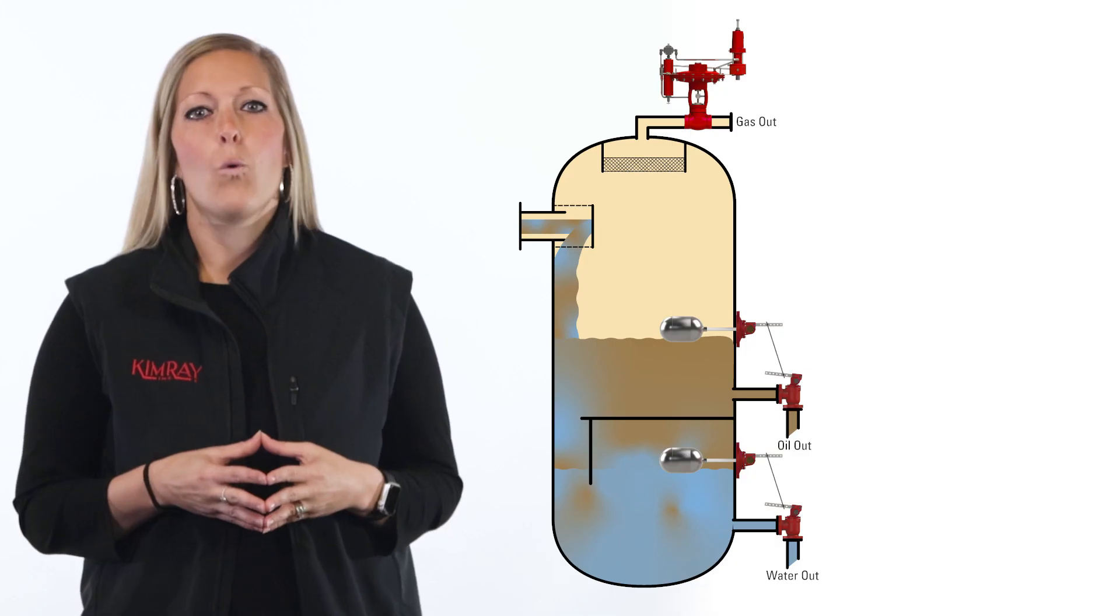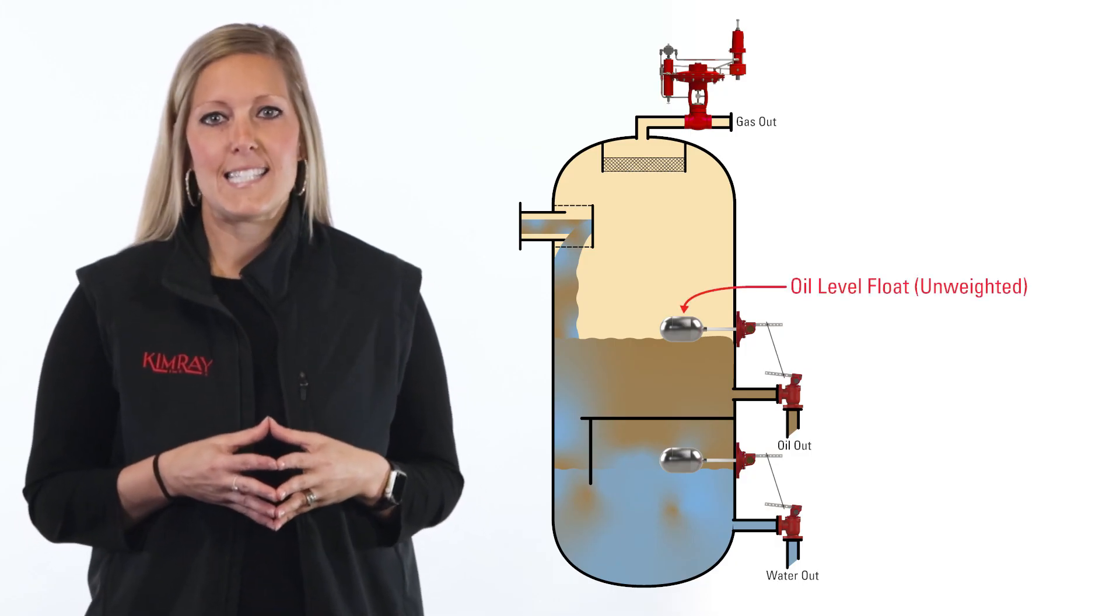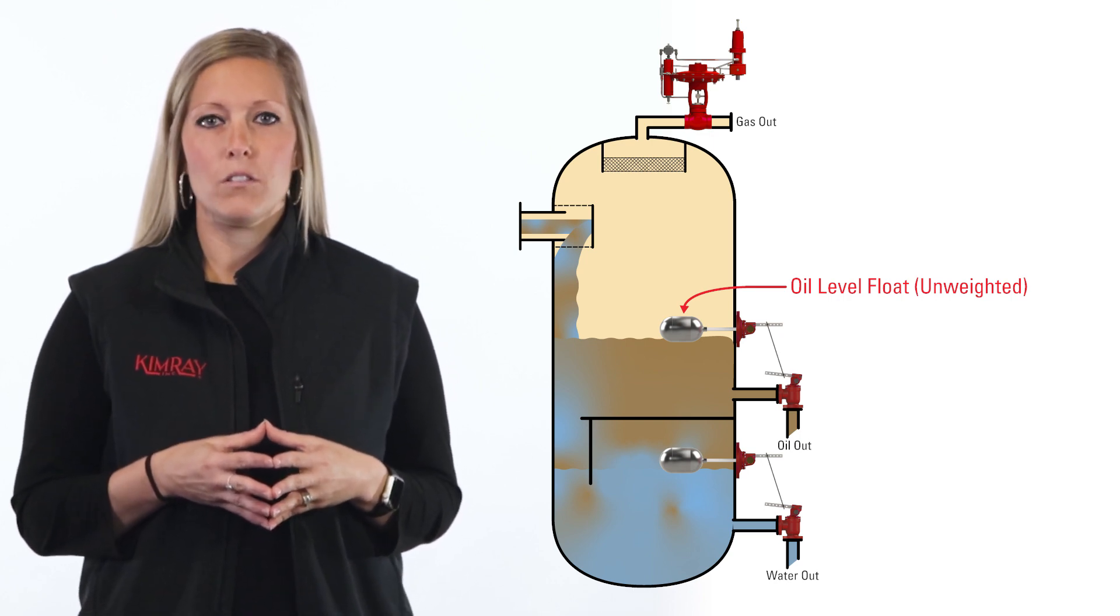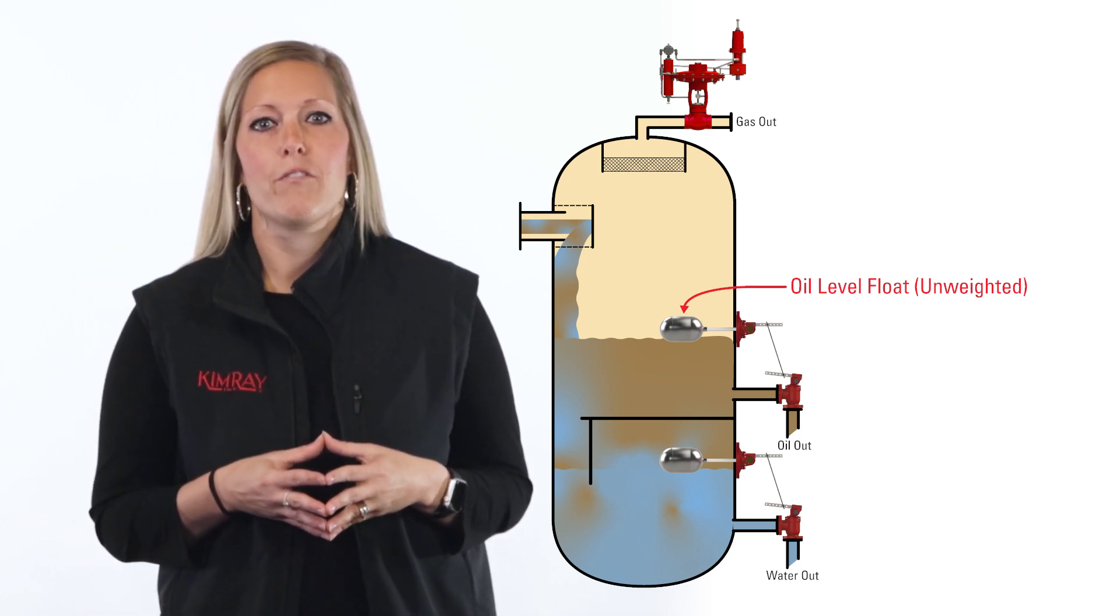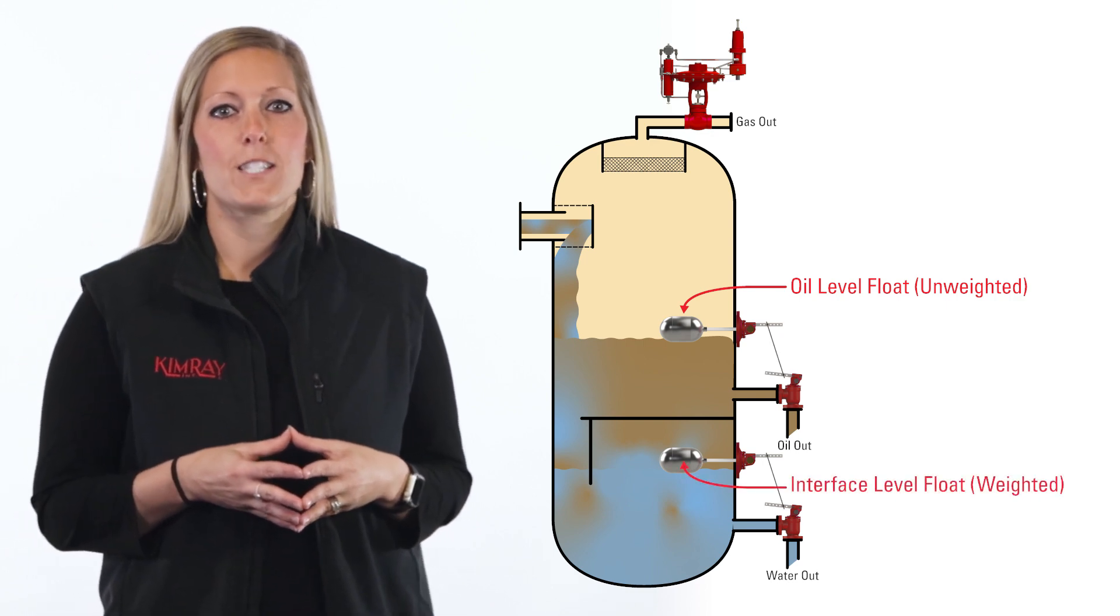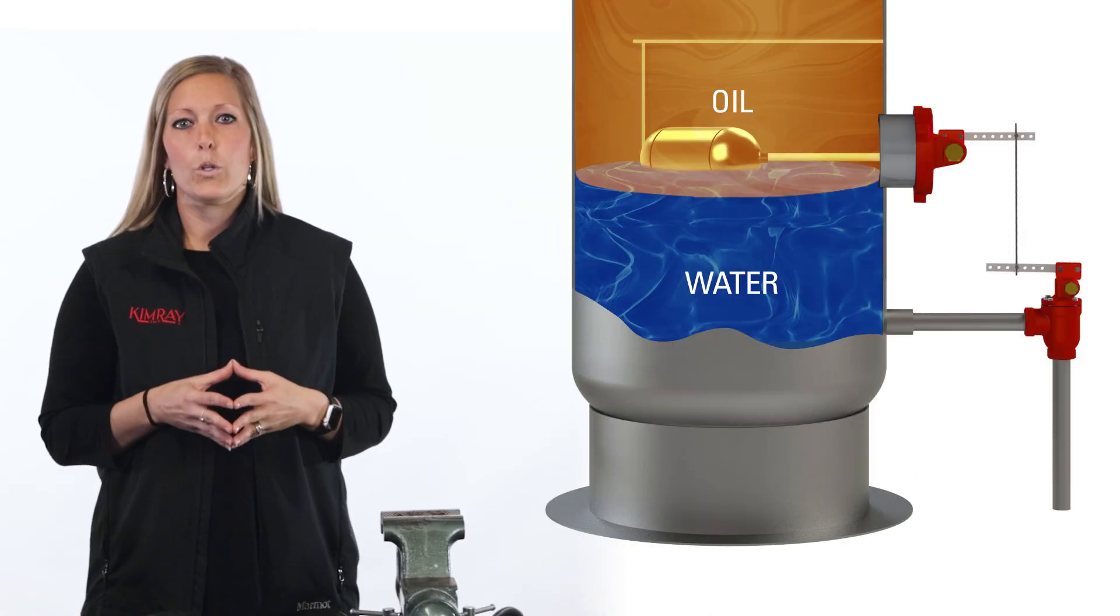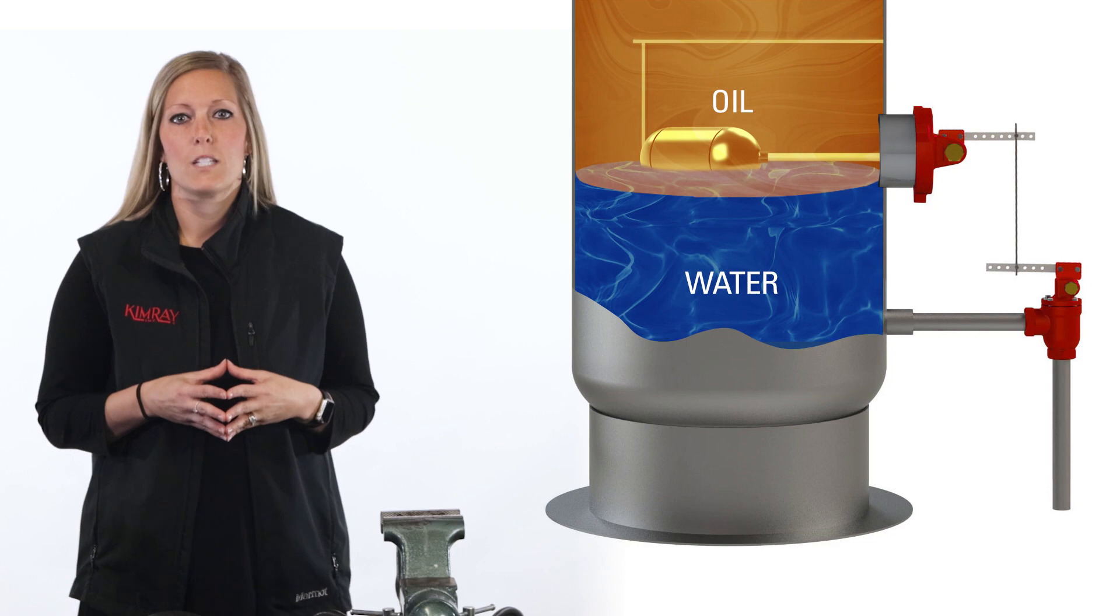On an oil and gas separator, producers often use two float-operated liquid level controllers. One will have an empty float that sits inside the vessel at the top of the oil, which will open the dump valve when the level reaches a set height. A second float will sense the interface level. In order to sink through the oil, this float must be weighted.